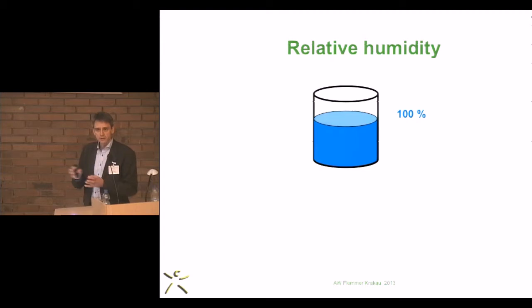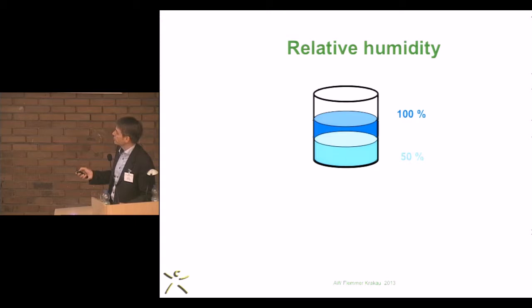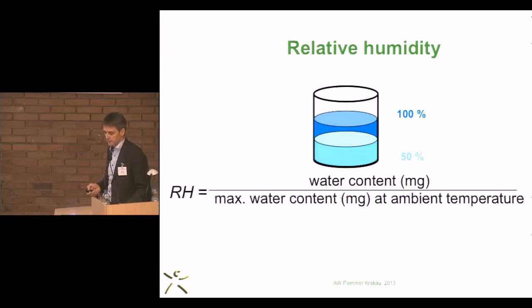We only adjust the relative humidity in our heated humidifiers, in our incubators, but actually we need to know how much water is in there in order to really determine whether we reach what we want to reach. Because if the relative humidity is decreased, the amount of water in this volume of gas is reduced. The relative humidity is calculated as the actual water content in this volume divided by the maximum content of water we could achieve if we would have 100%. Is that concept clear, or did anybody not understand that? It's not so difficult, right?